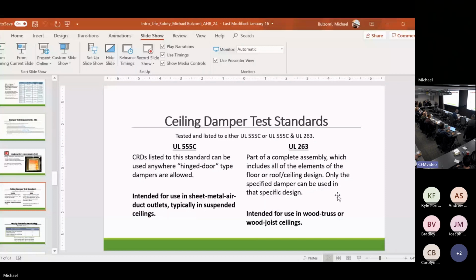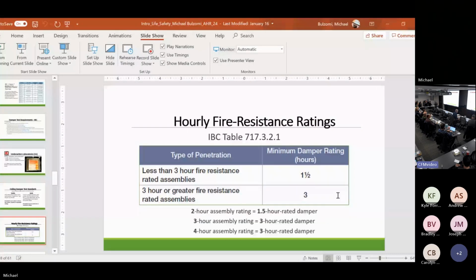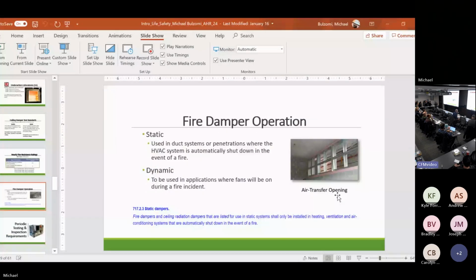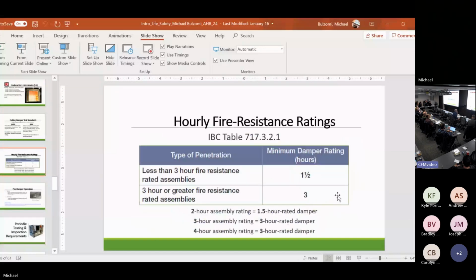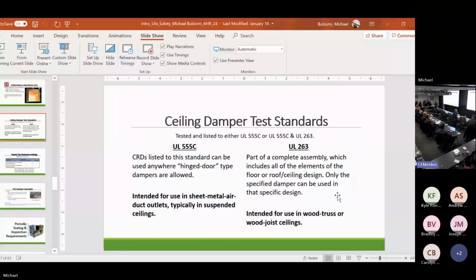If I'm in a drop ceiling, T-bar ceiling, it's what we call, wherever there used to be a hinged door type damper. Anyone familiar with what a hinged door type damper is? No? Okay, cool. I got a picture of it. Right. This is my ASHRAE presentation, sorry. This is a different version. Hinged door type damper: contractor takes a metal plate, an insulated box, puts a fusible link on it. That plate would be attached to the top of the box. And when that link melted, the plate would just fall closed. There's your old school ceiling radiation damper.